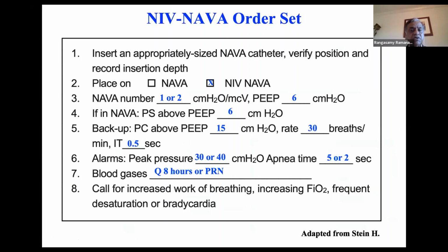So you can have a standard order set like this and insert the appropriate NAVA catheter, verify the position by looking at the EKG tracing. The blue lines are in the second and third channel. Put NAVA or NIV-NAVA. NAVA number, you start at 1. Usually you don't have to start at 2. I just put the range. PEEP of 6. Pressure support above PEEP is 6 for spontaneous breathing. Backup pressure control, PIP, 15 above PEEP. Rate 30, I time 0.5. Alarm for peak pressure, 30 or 40. If the baby keeps on triggering the alarm, just go to 40. Sometimes babies take a big breath, recruitment breath or sigh breath.